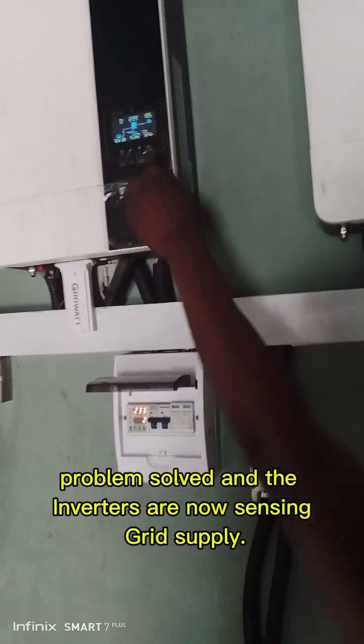So after we have separated the contacts, we want to check if the fault still persists. So I think it has stopped. So it means that is the issue they were having before. The inverter was not charging very well.